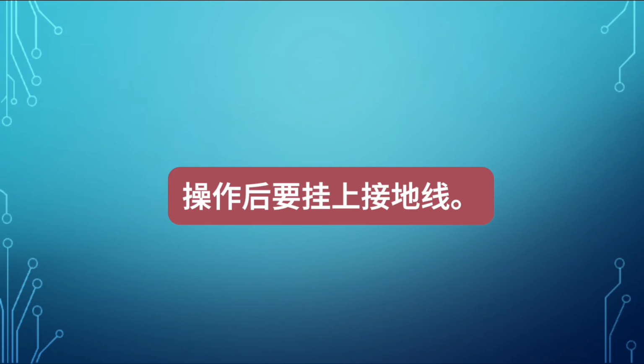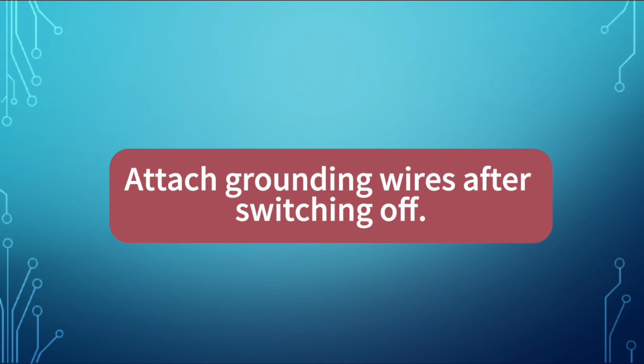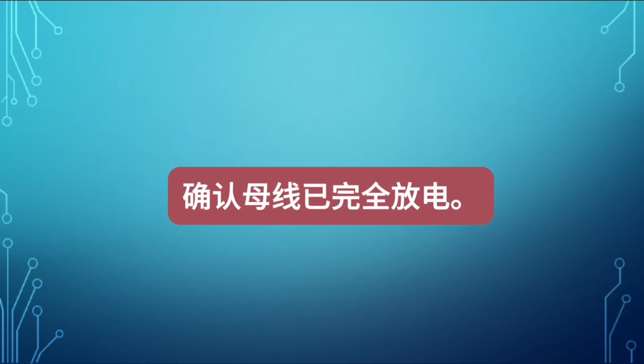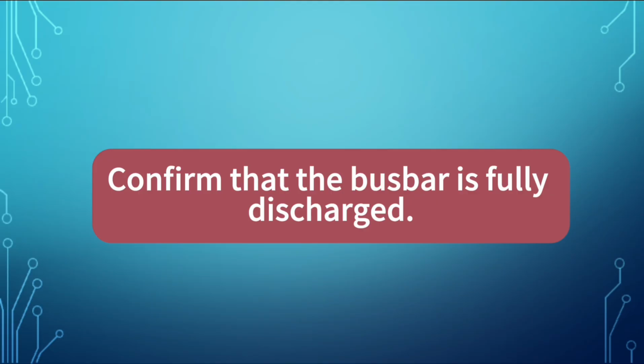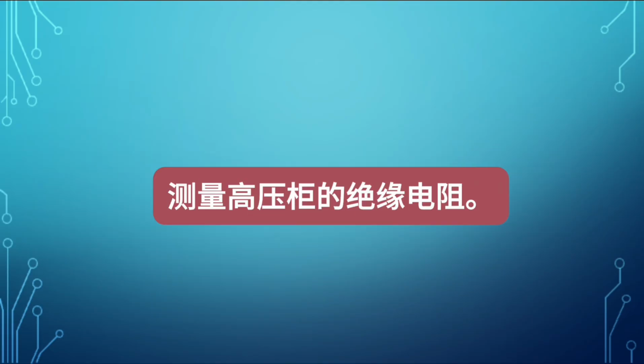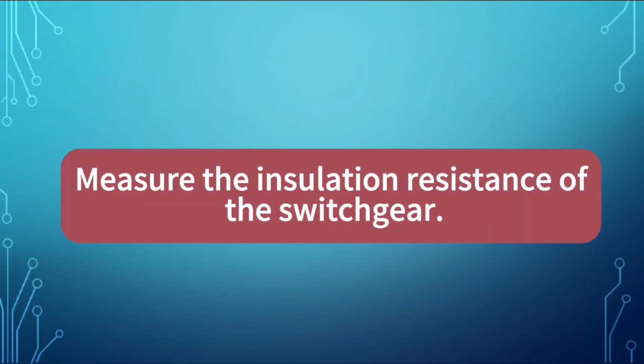Attach grounding wires after switching off. Confirm that the bus bar is fully discharged. Measure the insulation resistance of the switch gear.